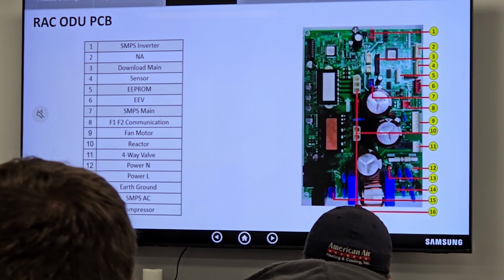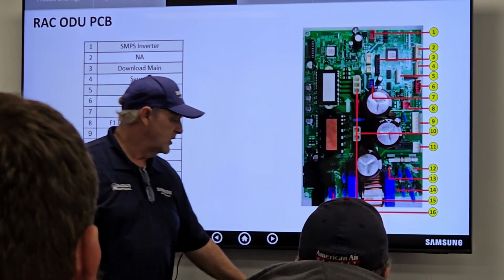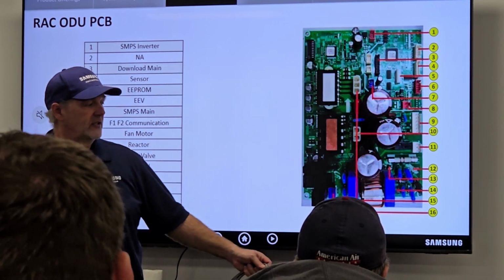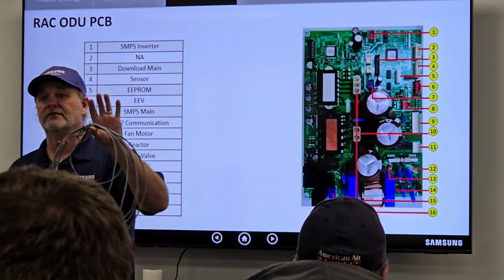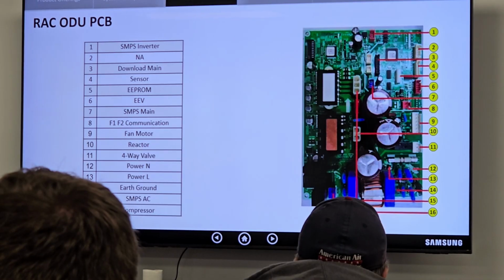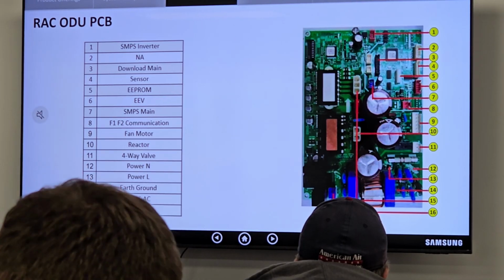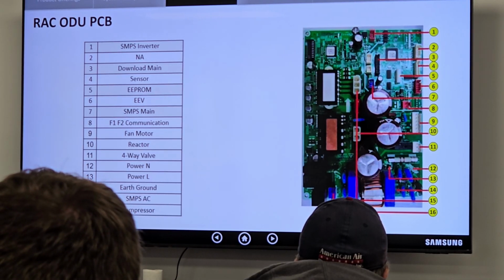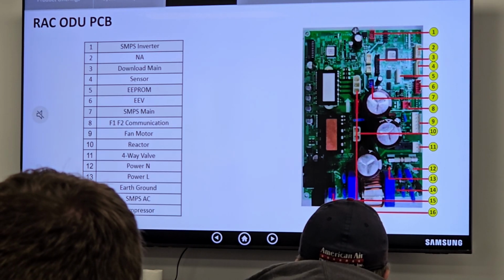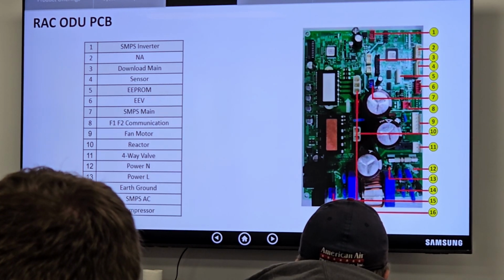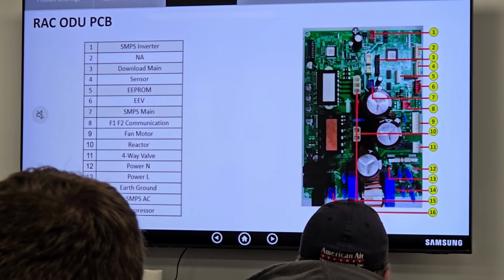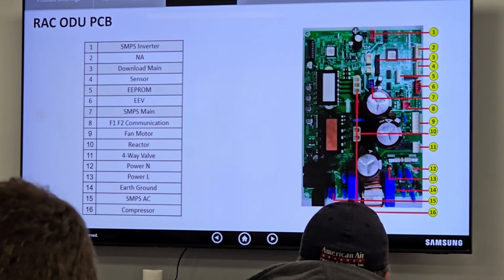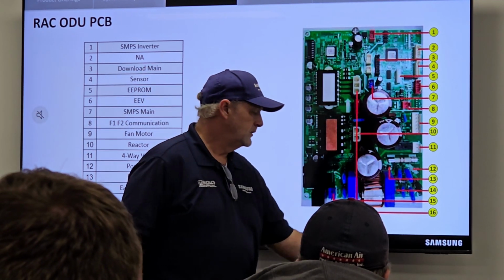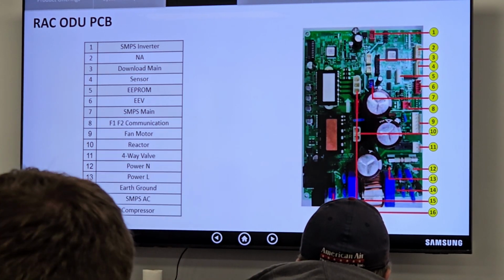Most of the time what you'll see on a standard RAC product is this gets tucked up underneath the line set so the UV can't get to it. If it's sitting on top, the UV will deteriorate the jacket over time. Most of the time it comes down the chase with the line set, then gets strapped up underneath the line set so it can't be seen, and then brought into the product from there. But it is a separate feed because of communication.